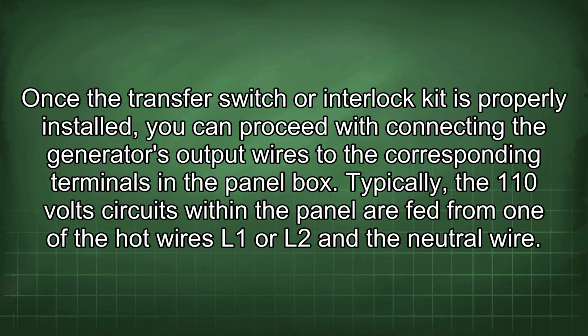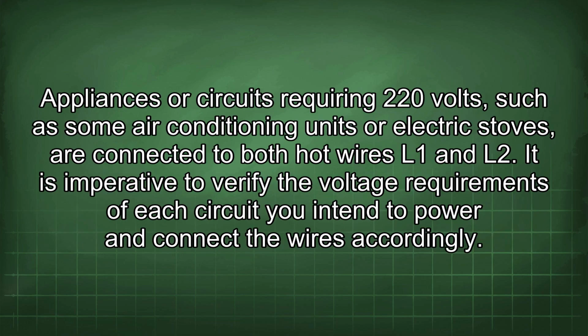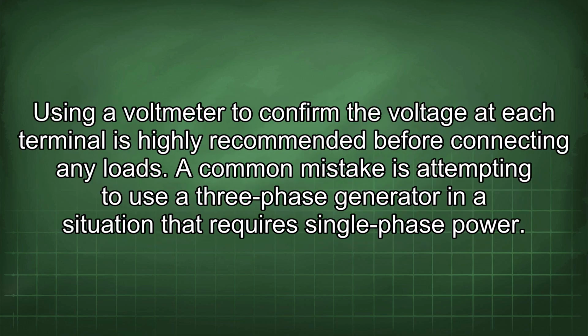Typically, the 110 volt circuits within the panel are fed from one of the hot wires, L1 or L2, and the neutral wire. Appliances or circuits requiring 220 volts, such as some air conditioning units or electric stoves, are connected to both hot wires, L1 and L2. It is imperative to verify the voltage requirements of each circuit you intend to power and connect the wires accordingly. Using a voltmeter to confirm the voltage at each terminal is highly recommended before connecting any loads.